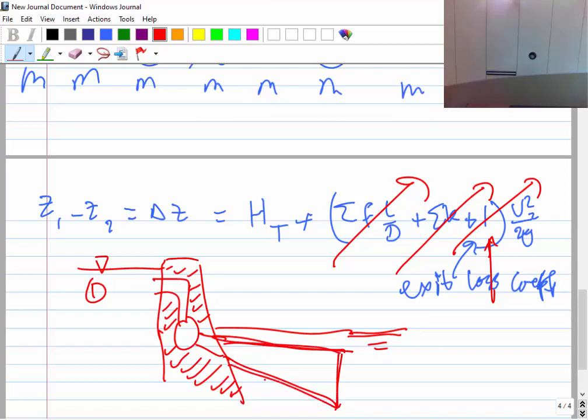They call this a draft tube. So the exit of the turbine, rather than just having a pipe, they make it really big. And this is not just energy-wise, you are increasing the energy output by decreasing V2, but it's also because you don't want what? Erosion.